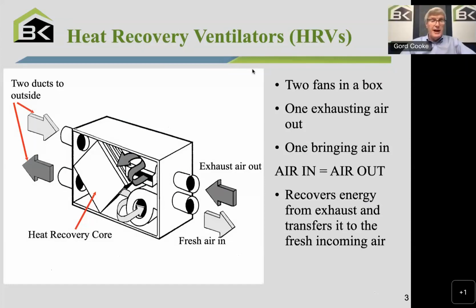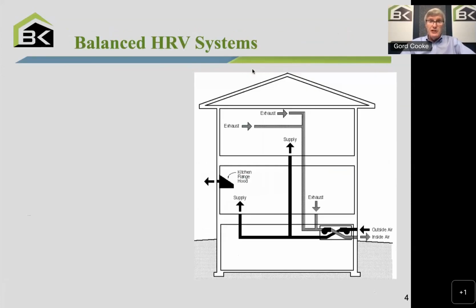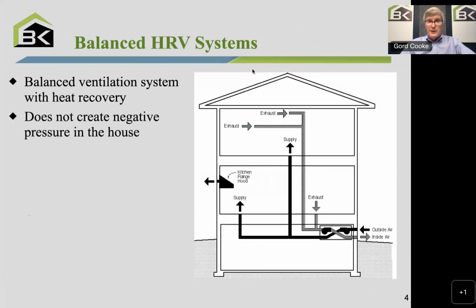So just wanted to highlight that this is a pretty straightforward box. In terms of maintenance, you can start to think there's really only 2 or 3 moving parts. There's those 2 fans. We're going to show you what's called a damper, a defrost damper. But generally speaking, they're pretty simple devices when you open them up. And they're installed in a couple of different ways. Typically, these are balanced ventilation systems. That is, the amount of air coming in is the same as the amount of air going out. And that's actually what we want so that we don't backdraft appliances, create negative pressure in houses.